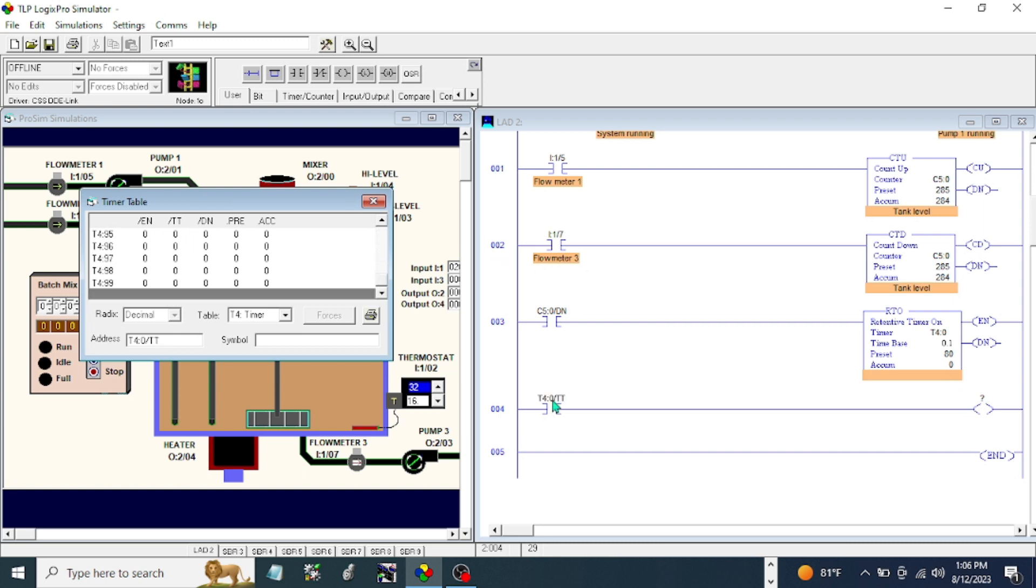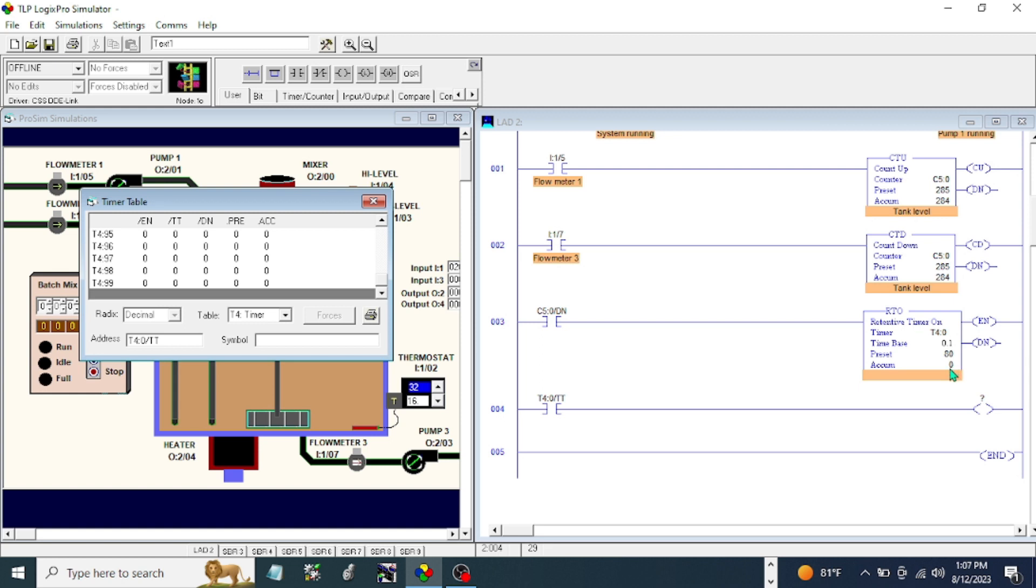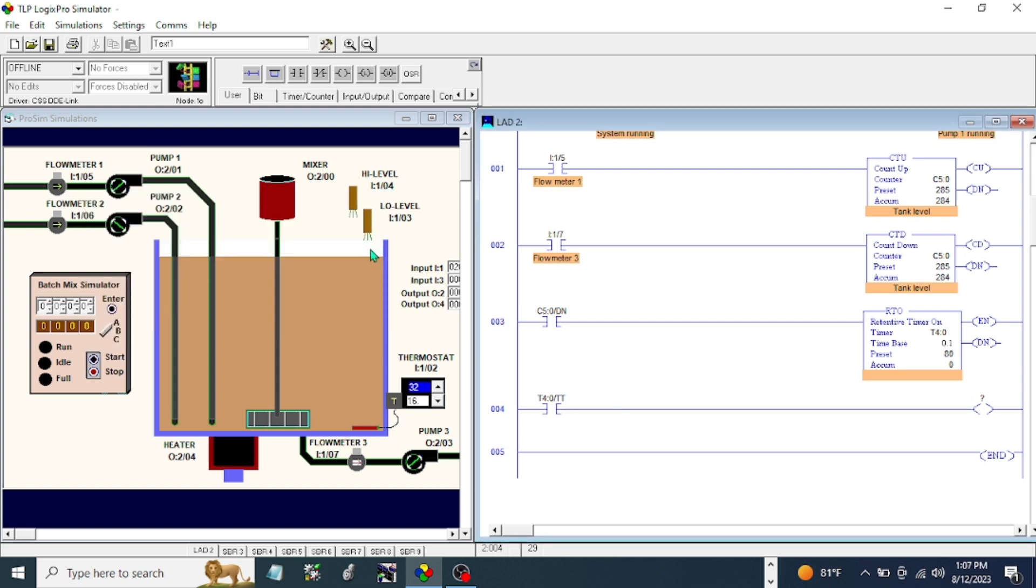The preset value is eight seconds because we have a time base of 0.1. The timer timing bit for our retentive timer, how it works is when this retentive timer is energized, this one will be on until the accumulation value is equal to our preset value. Once the accumulation value is equal to the preset value, this bit will open.